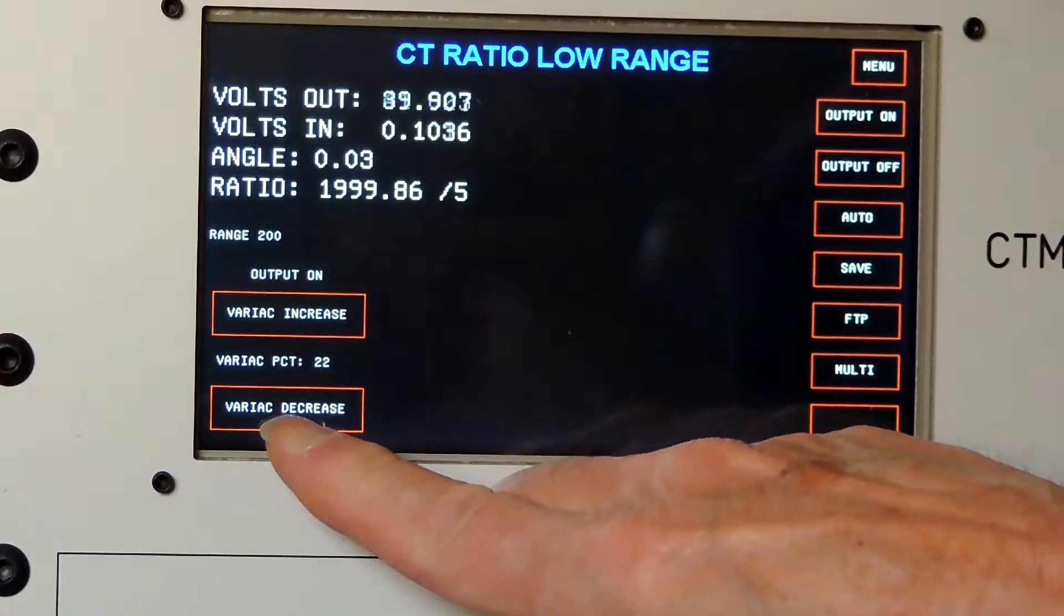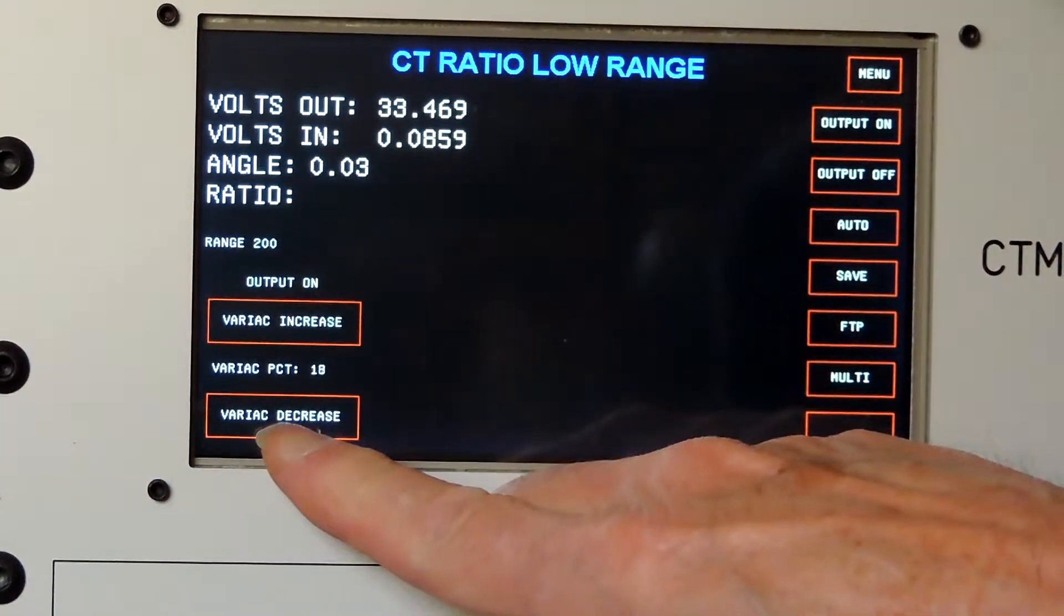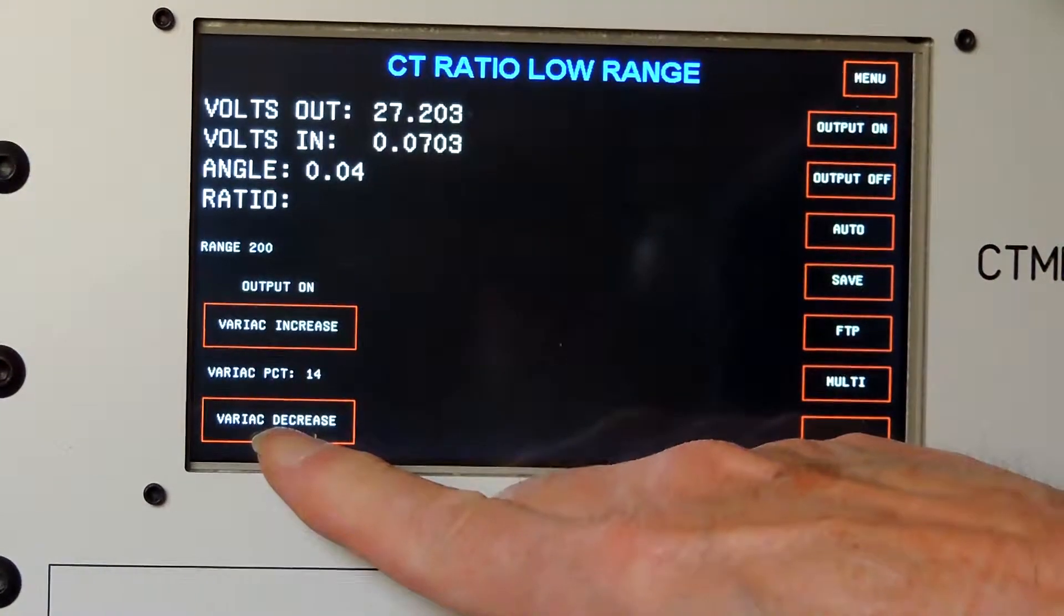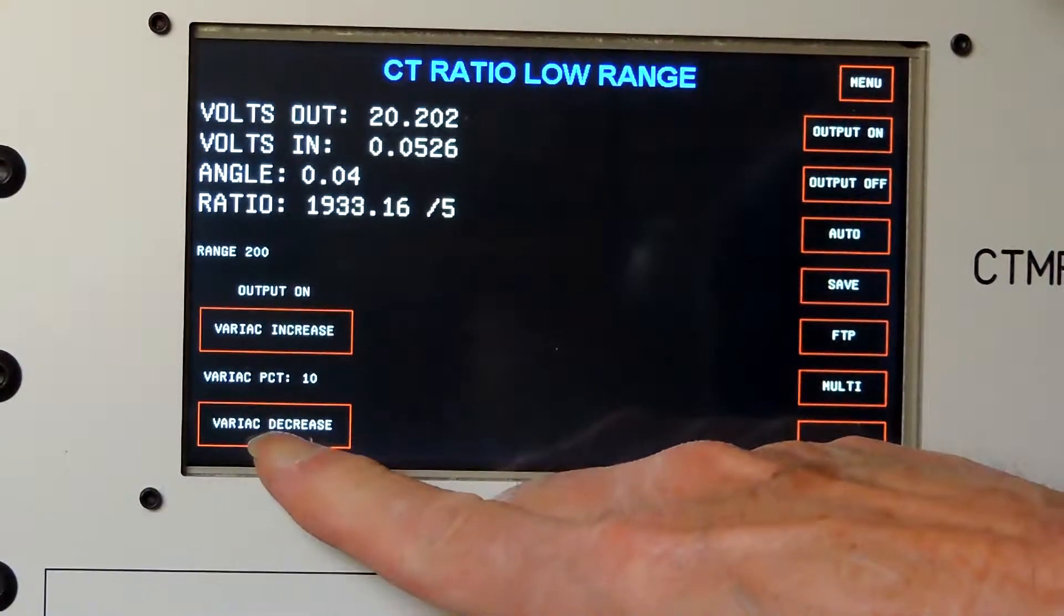So now I will run the variac down. You don't want to cut it off with it energized. I don't want to leave any residual magnetism in there, so run the variac down to 0.